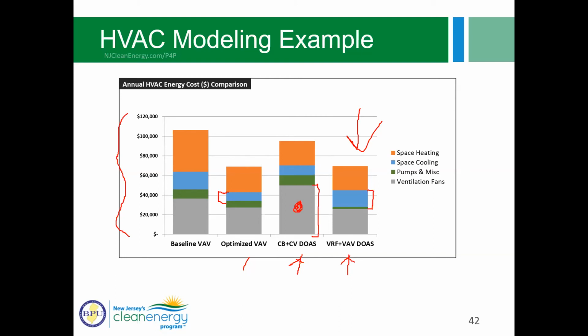And lastly, the other thing I thought was interesting about this analysis was, compared to the optimized VAV option, the chilled beam and constant volume DOAS had higher pumping energy in green. That's right here. And I think that's because of the increased pressure drop due to all of the coils associated with the chilled beam system. So, yeah, interesting analysis. This is always fun. I love it when a client wants us to incorporate this into the modeling process. And I think it's extremely beneficial for the clients, especially when you incorporate first cost and some life cycle cost analysis as well to figure out which option is best.